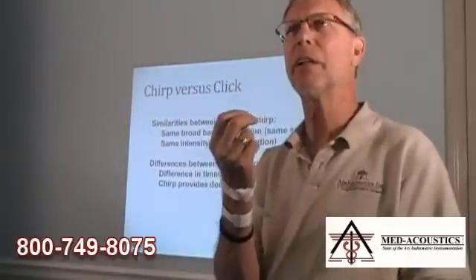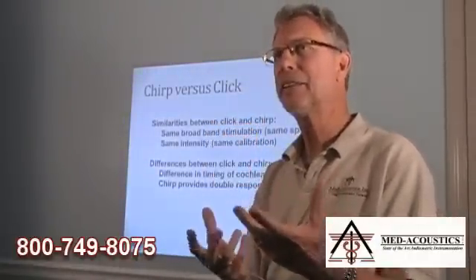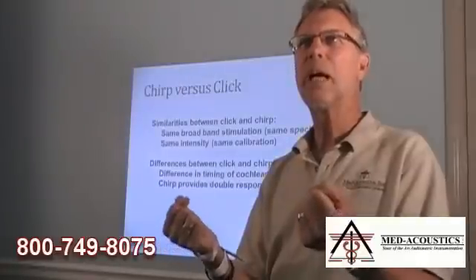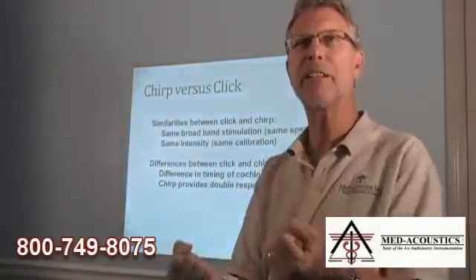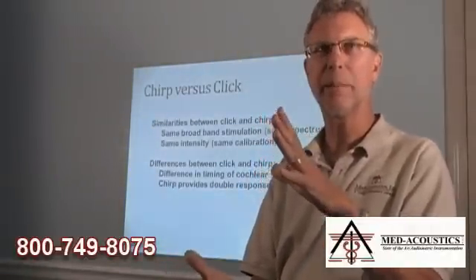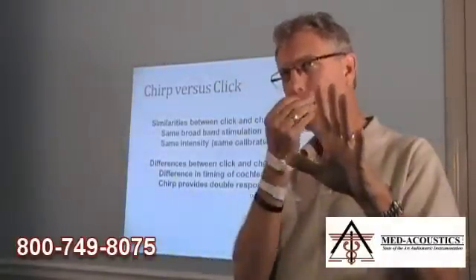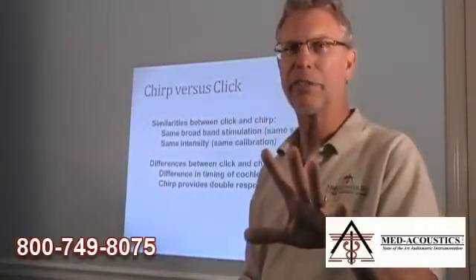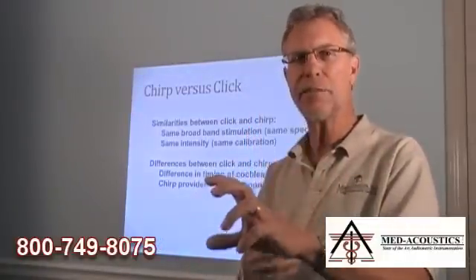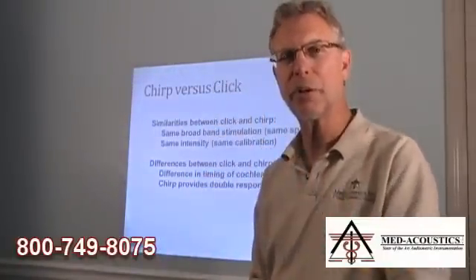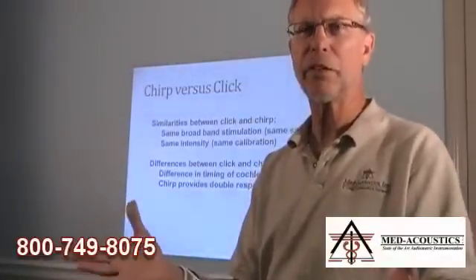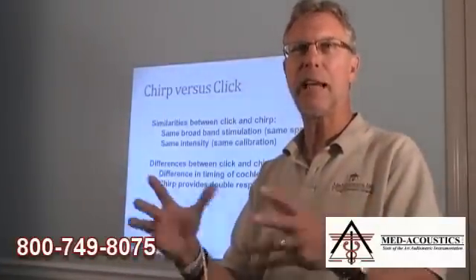In the case of the chirp stimulus, the needle is now not a needle — it's like a shovel. So we can do much less averaging to find it and get rid of the haystack, because it's so much bigger. There are several benefits to using a chirp instead of a click when doing a threshold ABR, and one of them is saving time. It saves a tremendous amount of time — it can be done in less than half the time it would otherwise take.